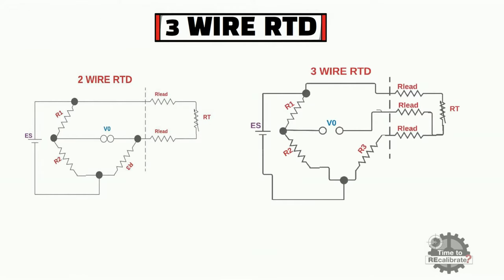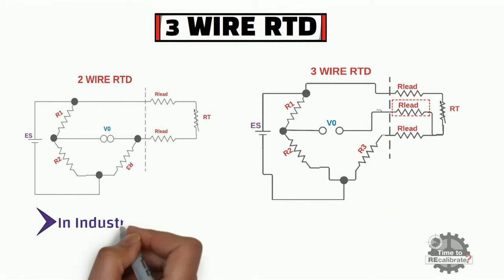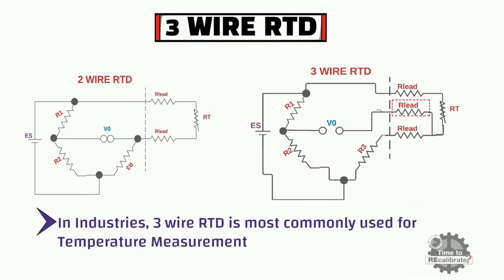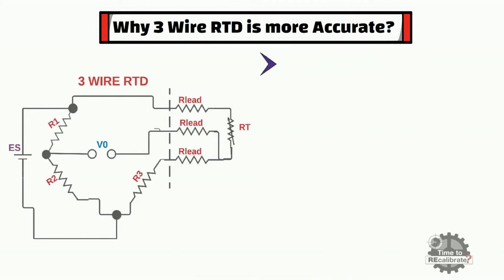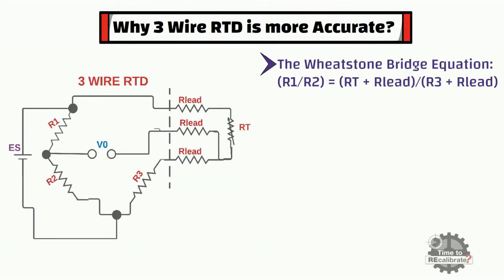3-wire RTD has an extra lead wire. This extra lead wire eliminates the effect of lead resistance in the circuit, which is not possible with 2-wire RTD. Hence, this is the reason that 3-wire RTD is the most commonly used RTD in industries. As you can see, this is the Wheatstone bridge equation for 3-wire RTD. In this equation, the numerator and denominator both contain R-lead, and because of this, the right-hand side ratio does not get affected by lead resistance — both lead resistances cancel each other's effects in the circuit.